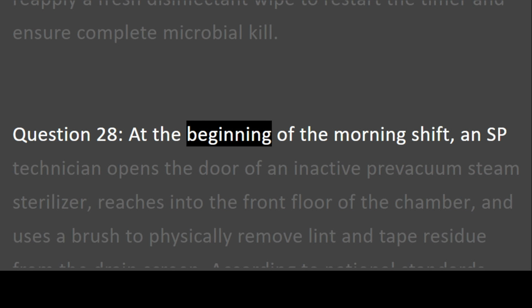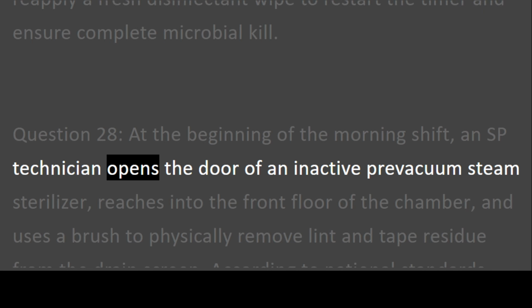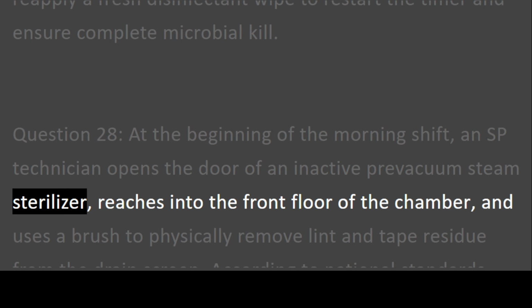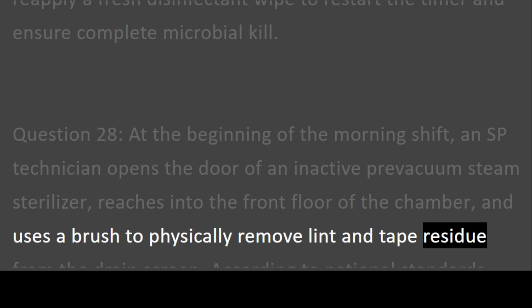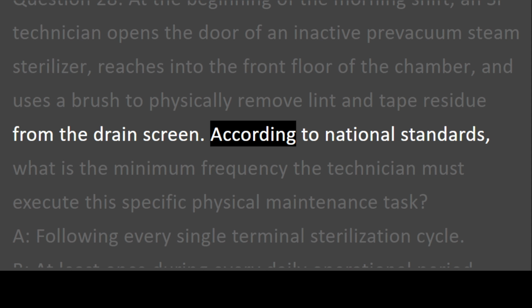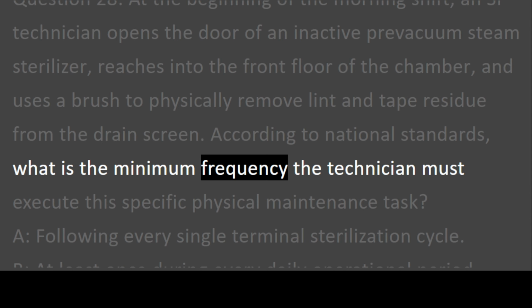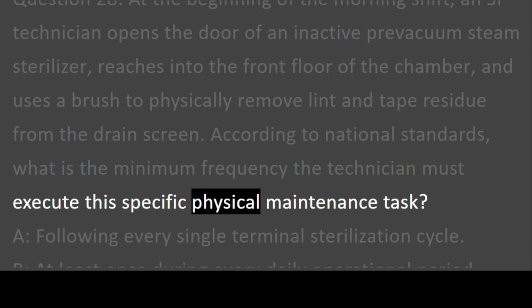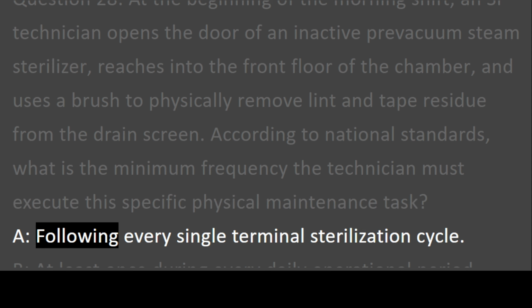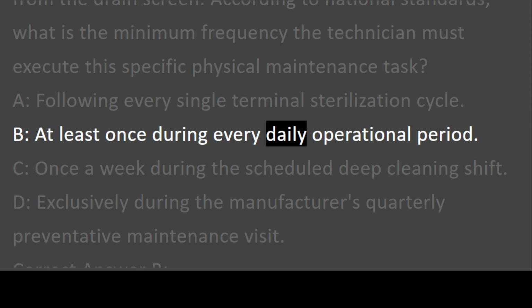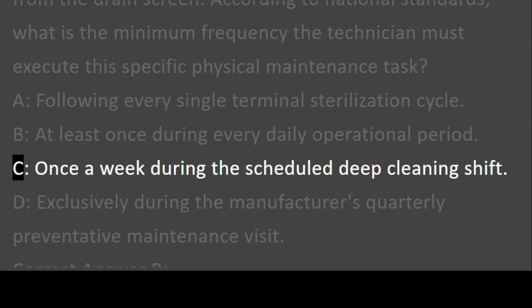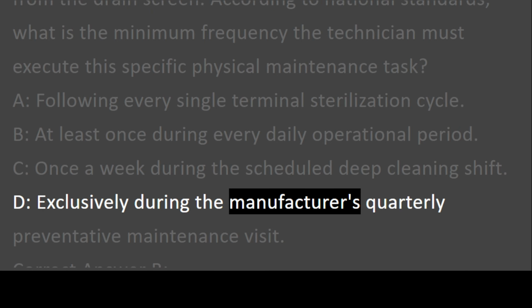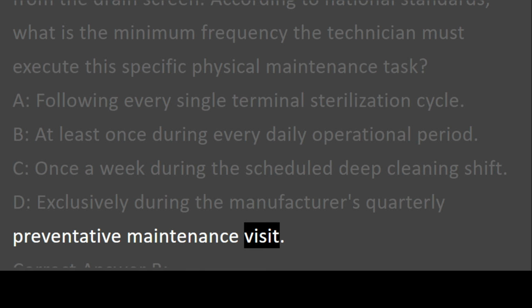Question 28. At the beginning of the morning shift, an SP technician opens the door of an inactive pre-vacuum steam sterilizer, reaches into the front floor of the chamber, and uses a brush to physically remove lint and tape residue from the drain screen. According to national standards, what is the minimum frequency the technician must execute this specific physical maintenance task? A. Following every single terminal sterilization cycle. B. At least once during every daily operational period. C. Once a week during the scheduled deep cleaning shift. D. Exclusively during the manufacturer's quarterly preventative maintenance visit.